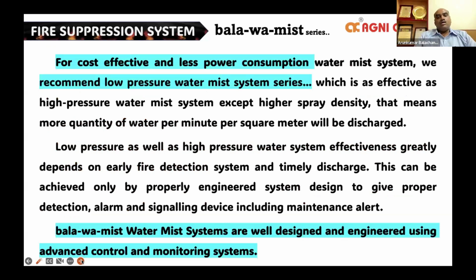However, for a very cost effective water mist with very low power consumption, we recommend going for a low pressure water mist system. The low pressure water mist system will be as effective as a high pressure water mist system, except that in a low pressure system, we need to have a higher spray density, which means in a low pressure system, the quantity of water per minute per square meter discharged will be more than in a high pressure system. Low pressure as well as high pressure system effectiveness greatly depends on the early fire detection and timely discharge.